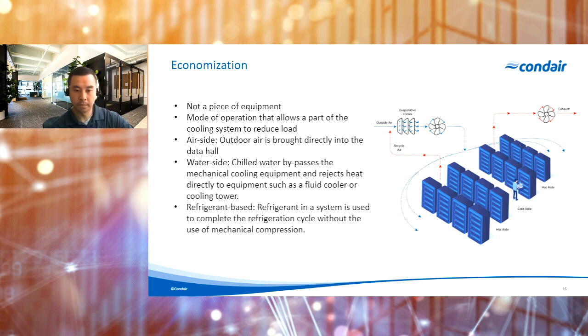The last one is refrigerant-based economization. In these types of systems, refrigerant in a system such as a direct expansion system is used to complete the refrigeration cycle without the use of mechanical compression. Though it is important to note that refrigerant-based systems tend to be more proprietary and can be unique to the specific supplier. And both the water side and refrigerant-based systems can still definitely benefit from the use of pre-cooling to increase the potential hours of economization by improving outside air conditions.